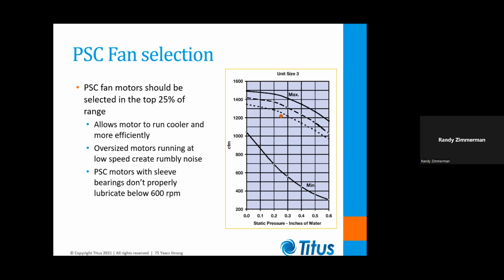Now, when I'm selecting PSC fans, most people select with a discharge pressure assumed to be 0.25 inches. That seems to be kind of standard in the industry. I actually have found that discharge pressures are usually much lower than 0.25 because people tend to over-engineer their discharge ductwork. But if we just stick with the standard 0.25 selection point, I try to select in the top 25% of a PSC fan motor curve because I know that I get my highest efficiency and cooler running motor up at the top end of the curve, and that's going to make the motor last longer, run cooler, and run more efficiently.